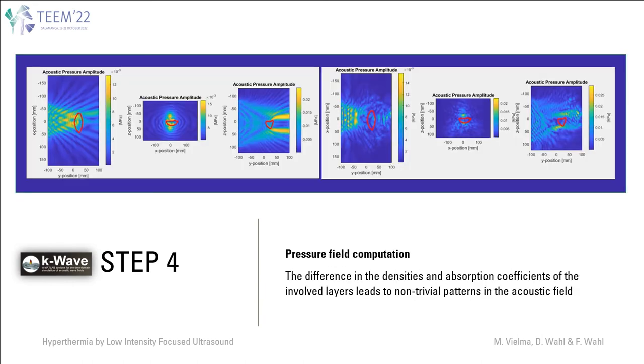Once we have control of the geometries with their corresponding acoustic and thermal properties, we can perform pressure field computation, and this would be our step 4. The left image here shows the acoustic pressure generated by the bowl when directed towards the prostate, represented by the red contours, ignoring the effect of layers other than the prostate. The right image shows the result for the same configuration considering the skin and pelvic bone layers. The difference in the densities and absorption coefficients of the involved layers leads to non-trivial patterns in the acoustic field.